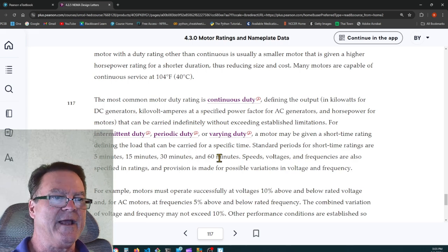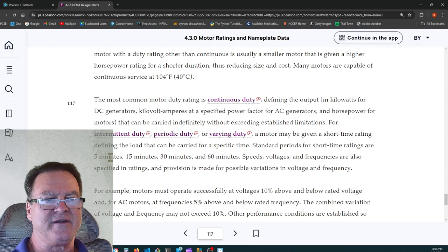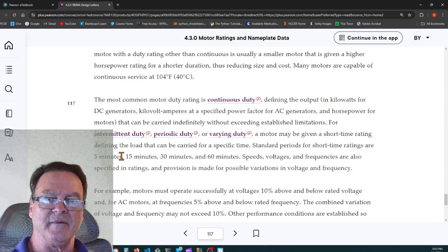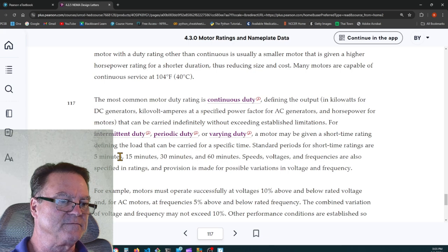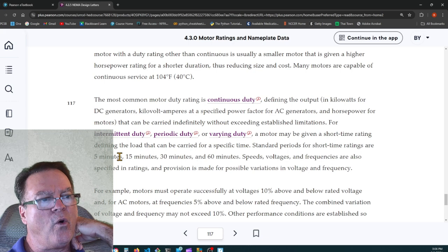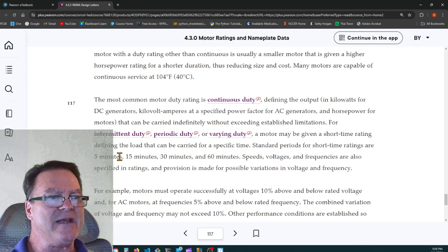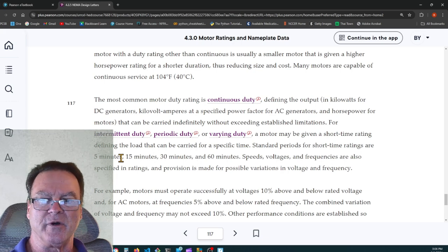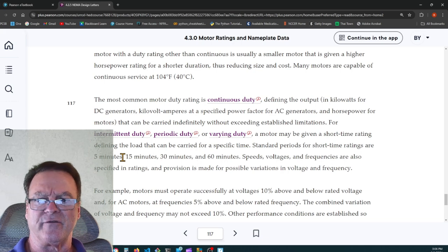So if you have a garage door opener, it's going to be intermittent duty. It's going to have a 5 minute rating. It doesn't take 5 minutes to put your door up or down. Every time that motor comes to rest, the bearings and the coils of the motor will cool off. It generates heat while it's operating, but as soon as you stop that motor, it starts to cool off very quickly. So if you open your garage door, change your mind and close it, and then change your mind and open it again, you're not going to burn it up. If you did that for a half hour, maybe you'd burn it up. But 3, 4, 5 times, you're not going to burn it up because it's intermittent duty and it can go for as long as 5 minutes in operation. And like I say, it's only running for about 15 seconds.